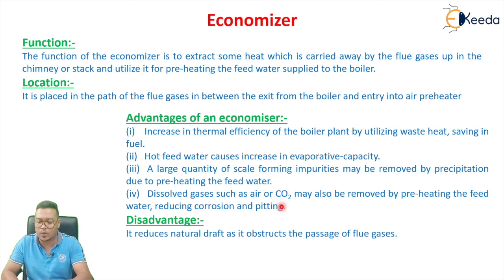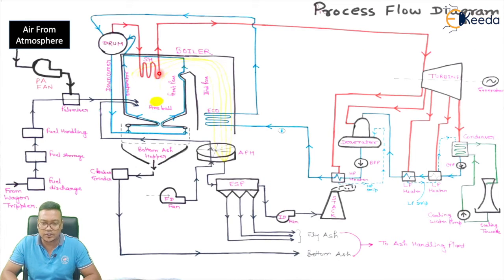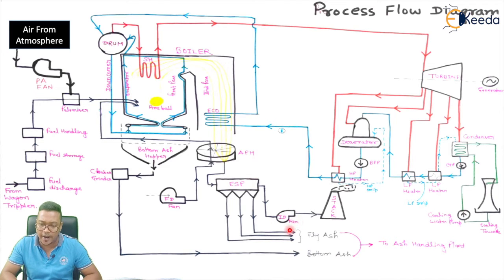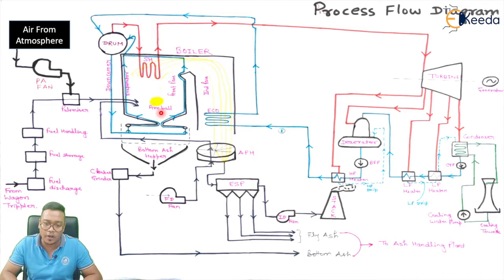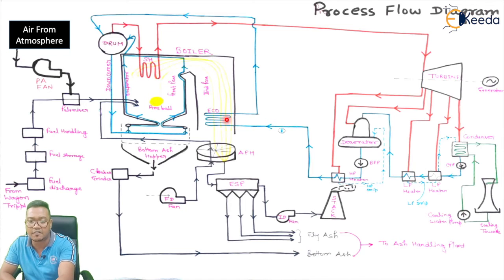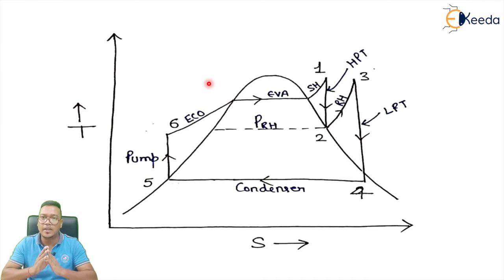What is the disadvantage of the economizer? Suppose the flue gas is flowing and the economizer is placed in its path — it increases the pressure loss. In a natural circulation system with no ID fan and no FD fan, this economizer increases the pressure loss of the flue gas as it flows through the second pass. This is the disadvantage of the economizer.